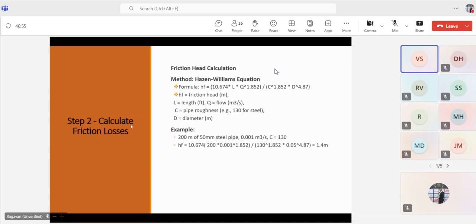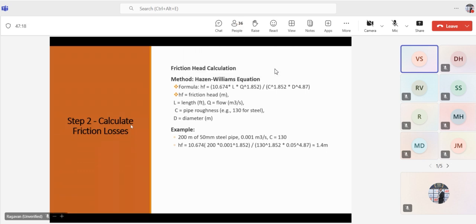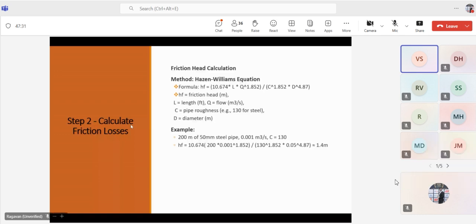In this calculation, the friction loss is in SI units, so it is in meters, and the length is in meters. The flow is in cubic meters per second. And C is a roughness factor, which varies based on the pipe material. If we are using the carbon steel pipe or the black steel pipe, it is around 130. And if you go for HDPE pipe, it will come to, I think, 150. Then the diameter, of course, will be in meters.